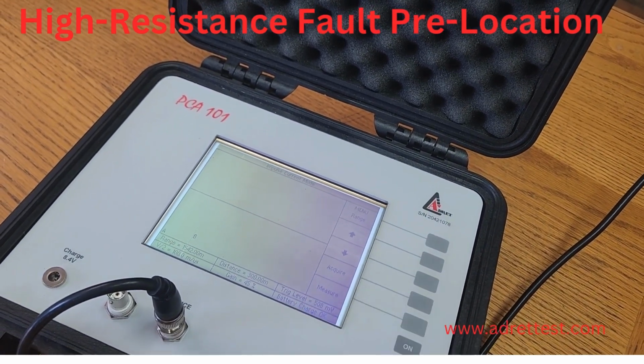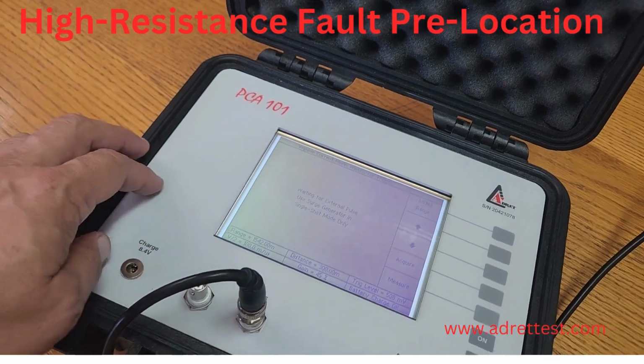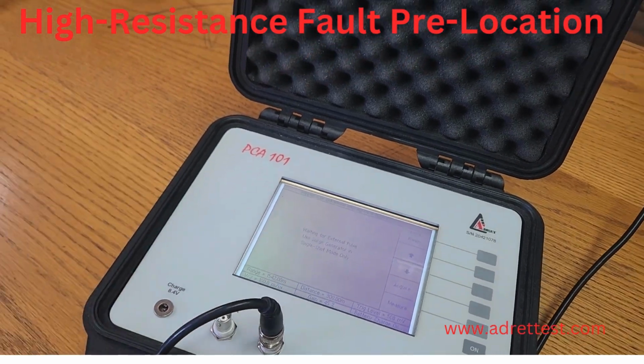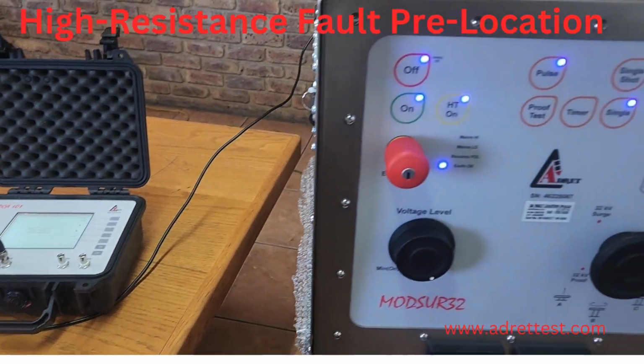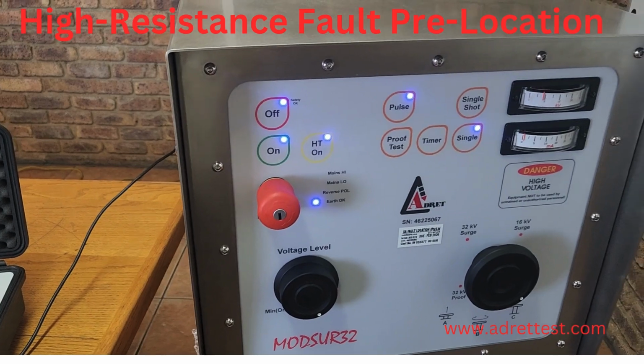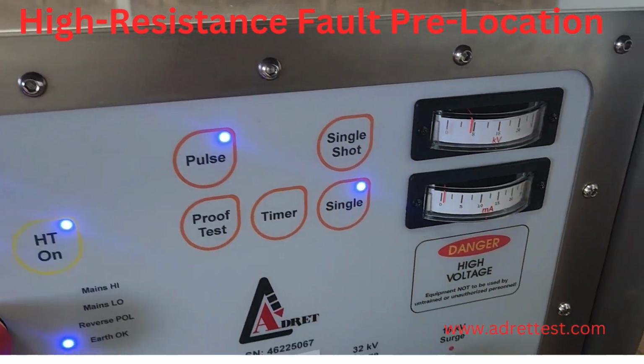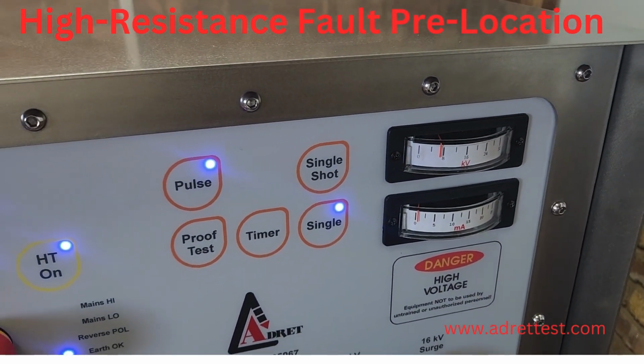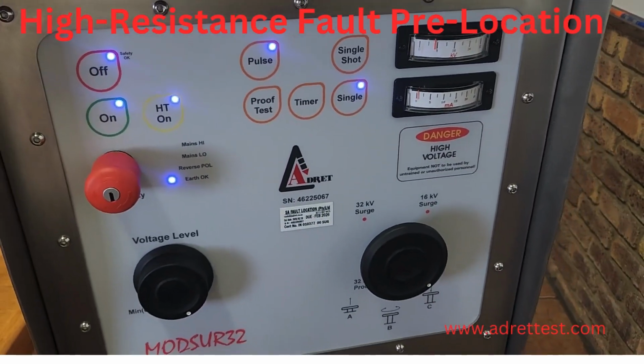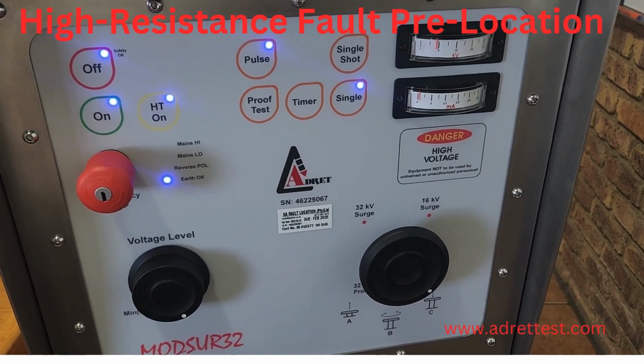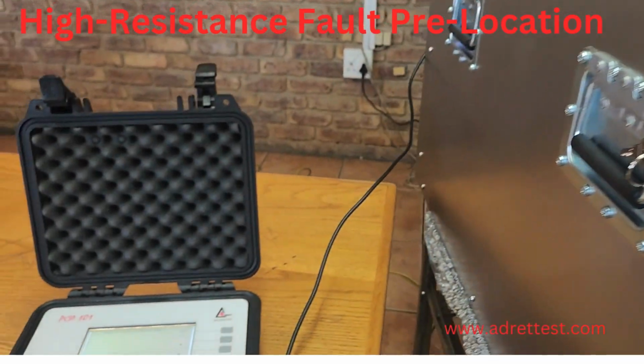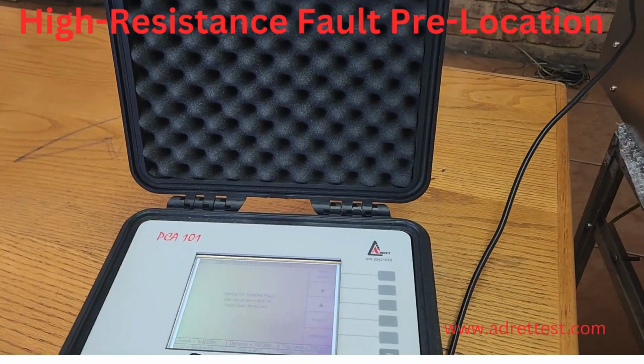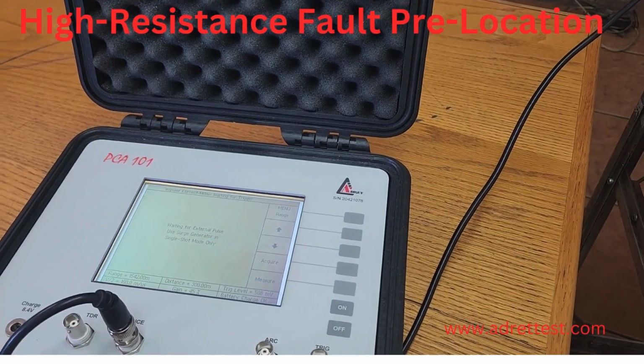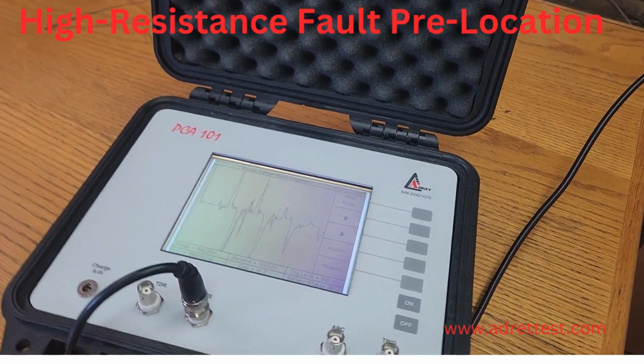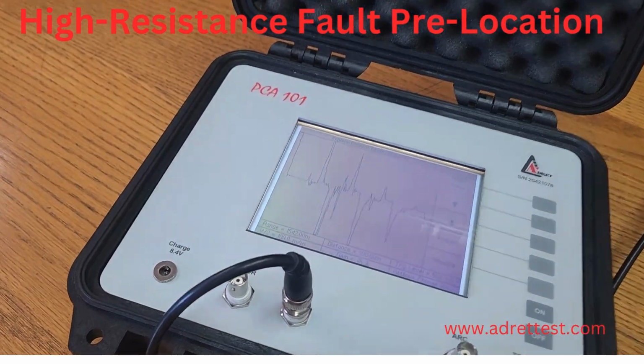But now, if we acquire our internal pulse of the unit, it's a bit small, so we are using an external pulse. The surge generator is set up to 8000 volt. I'm using the MODSUR32 2200 joule machine. And as I single shot it, you can see the graph.